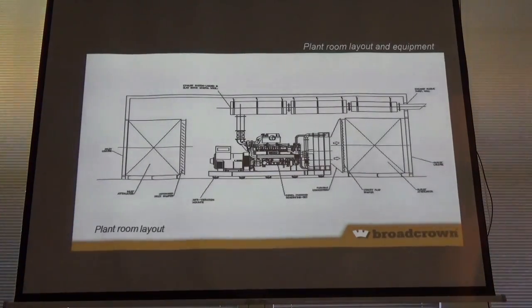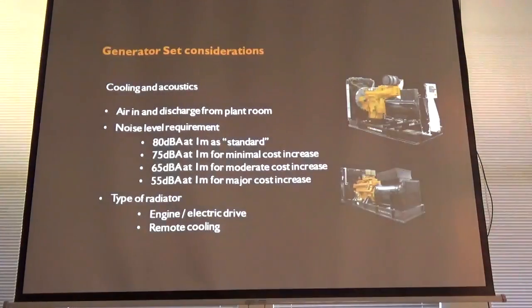So again, I'll feed back off the consultant: what is it, life safety? And they tell me the levels. But for a life safety unit, ask the question, what is an acceptable level, and they often do differentiate. But it's pointless if you've got a plant room with the life safety unit dedicated and then a tenant's unit sitting in the same plant room. You know, it's in context whether it's actually going to work or not, because they might wrap it overall. This is the maximum noise level required, because you've got both units running in there. You can't easily differentiate, of course, if they're both in the same plant room. So I've kicked that to death, really.